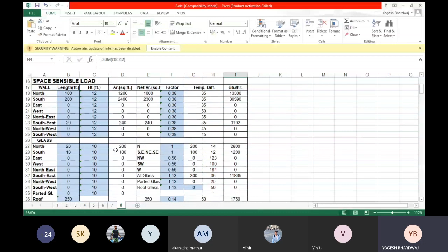Also notice this is the pressure which I am giving at the coil. For this fresh air, it is considering that 10% of the fresh air is directly coming to the room, bypassing the cooling coil. That's why I can see some heat there. So this is the total space sensible heat load. Then there is some safety factor for the space.